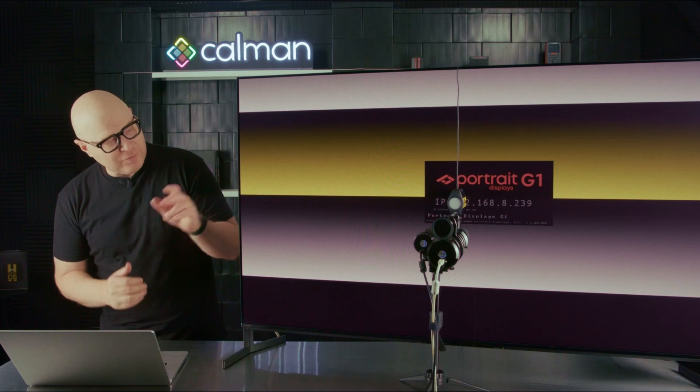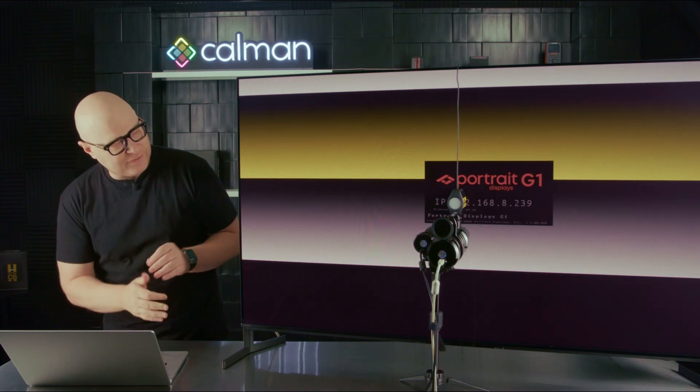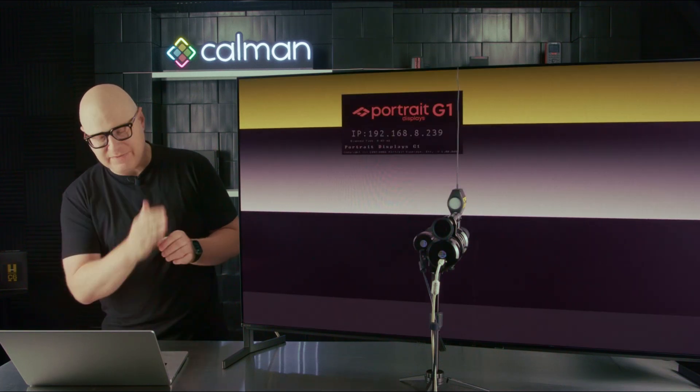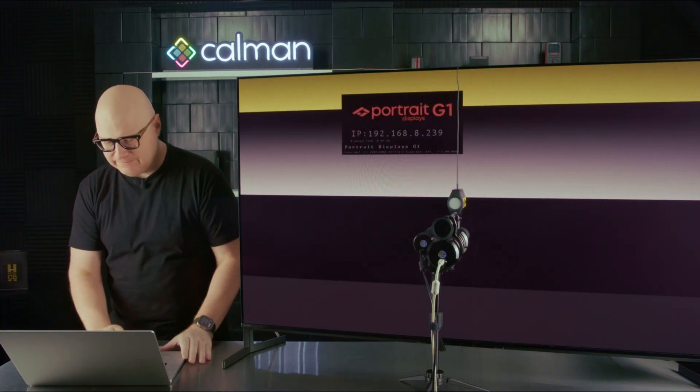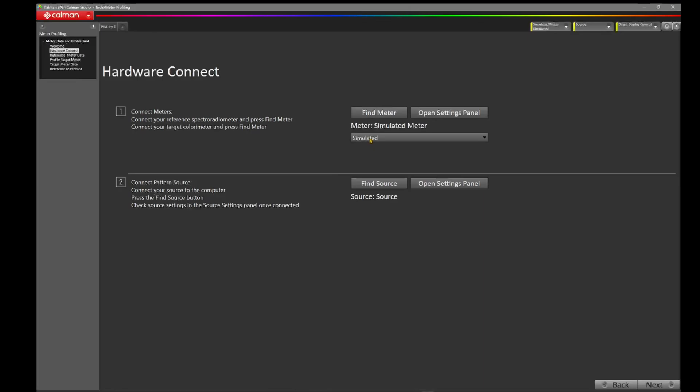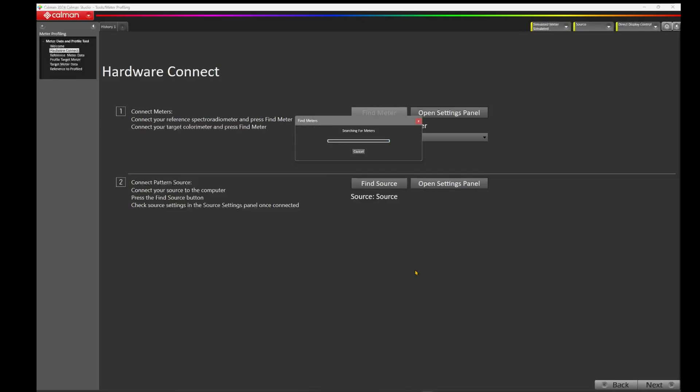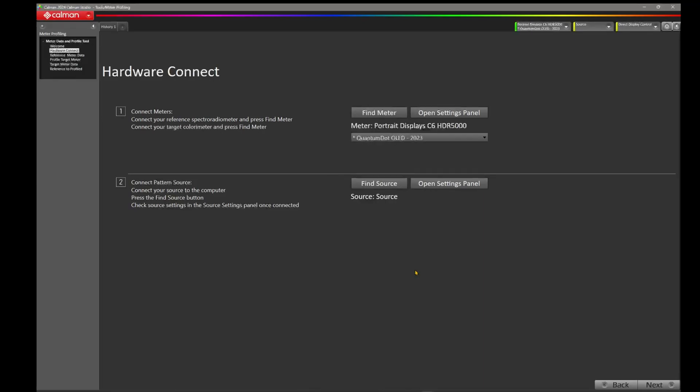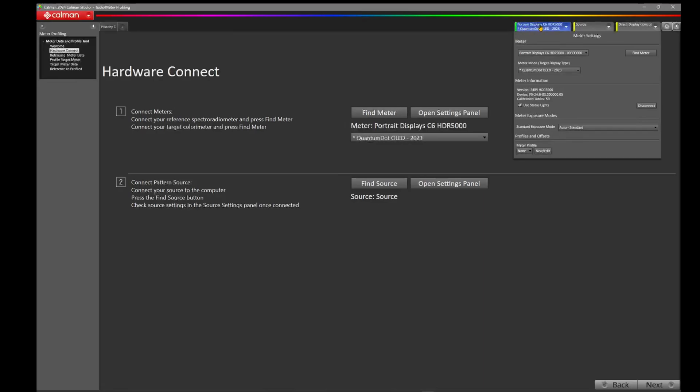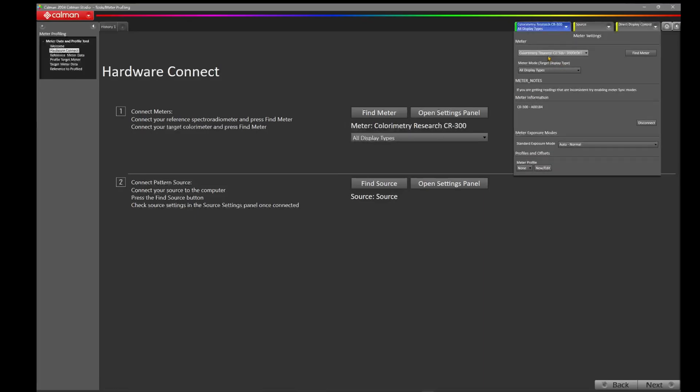We have two meters we need to connect to, the Portrait C6 and the CR300. Let's press Find Meter. My CR300 is on COM7, so I'm going to leave that set to COM7. Let's press Search. If we come up to the top right hand corner, you'll notice we've connected to the Portrait Displays C6 HDR5000. And if we click here on the meters, we've also connected to the Colorimetry Research CR300. I can easily toggle these here in the menu on the top right. I'm going to select the Colorimetry Research CR300.